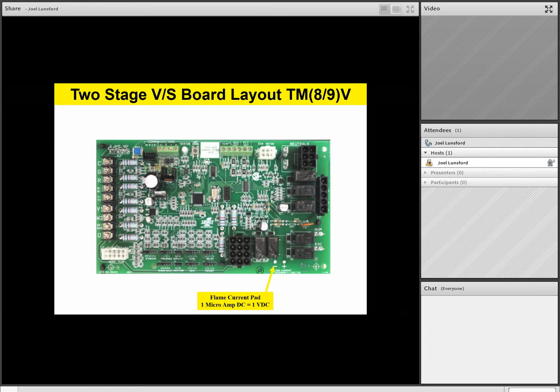This is built into the board, so all the technician has to have now to check his flame current is just a very common voltmeter, and he goes to DC volts, and 1 volt DC equals 1 microamp DC flame current. Now remember, team, flame current is very, very important so the furnace can continue operation. It has to be able to sense the flame, and 3.5 to 4 is the typical flame current. And again, if you've got poor grounding, it can start having reduced flame current. And so grounding is the #1 cause. I can't stress that enough. Grounding is the #1 cause of low flame current. So if you have poor grounding, you may have low flame current.